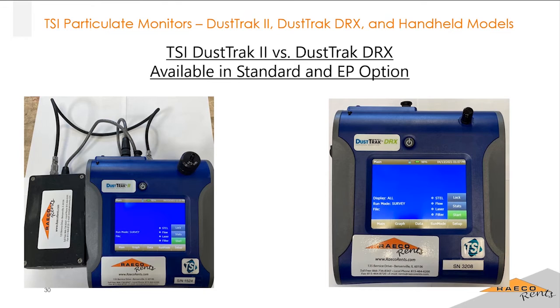So we do that relatively often. If you guys owned one and you're in the field and it's failing that zero calibration, that would be what you could do. You could clean out those mirrors. You could try changing filters as well. And actually you see on the DustTrak here, all those little indicators like filter, laser, flow. That'll tell you if a filter is overaccumulated with particulates. It'll tell you if the laser's gone bad. It'll tell you if there's an issue with the flow rate.